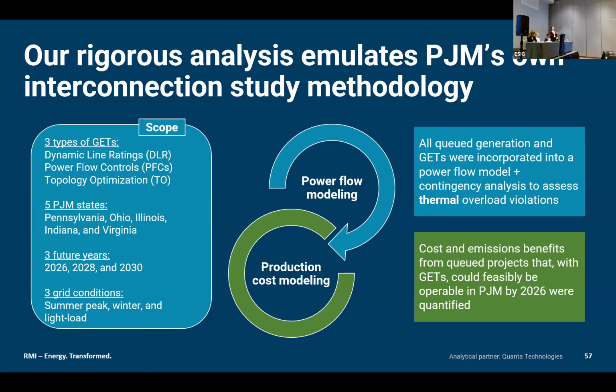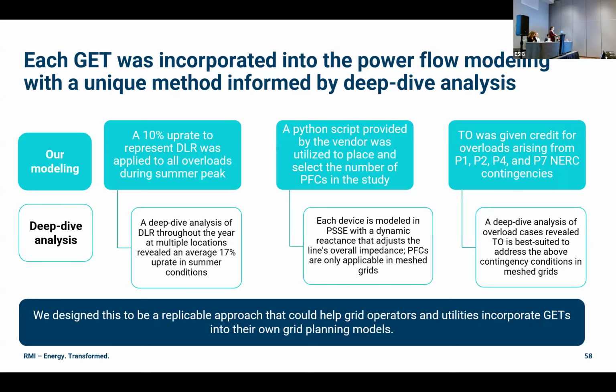So if a new generator were to come online in PJM's transmission grid and trigger a 10 or 20% overload violation, we assessed whether we could alleviate that violation with grid enhancing technologies. After that power flow modeling, we also conducted production cost modeling, or the 8760 economic dispatch analysis, to quantify the cost and emissions benefits from those grid enhancing technologies and new renewables.